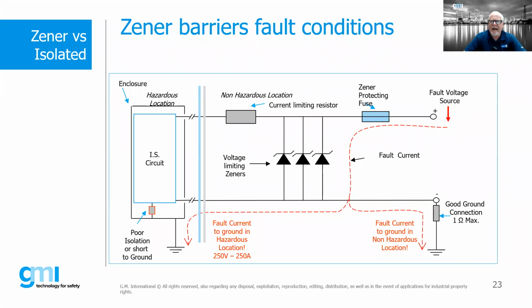Now, what can happen under a Zener barrier fault condition? We potentially could bypass the Zener diodes if the Zener diodes fail, although that's generally not the case. But if we had a fault condition potentially from the safe area, connected through that loop, we potentially could create a fault into the hazardous location, basically bypassing the Zener diode itself.